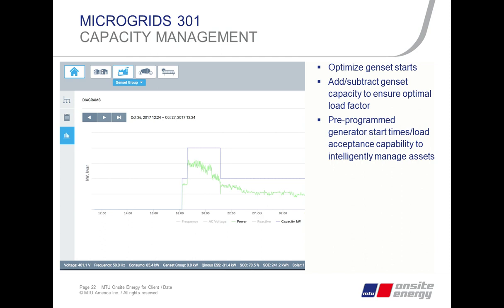For a certain number of hours we run both gensets, and as the load drops, we shut off one and keep the other running for the rest of the time. This is a great representation — you can see the percentage of generator capacity at the same time as the duration it's run, showing how we try to keep the generator as highly loaded as possible, and when we transition from one to the other.